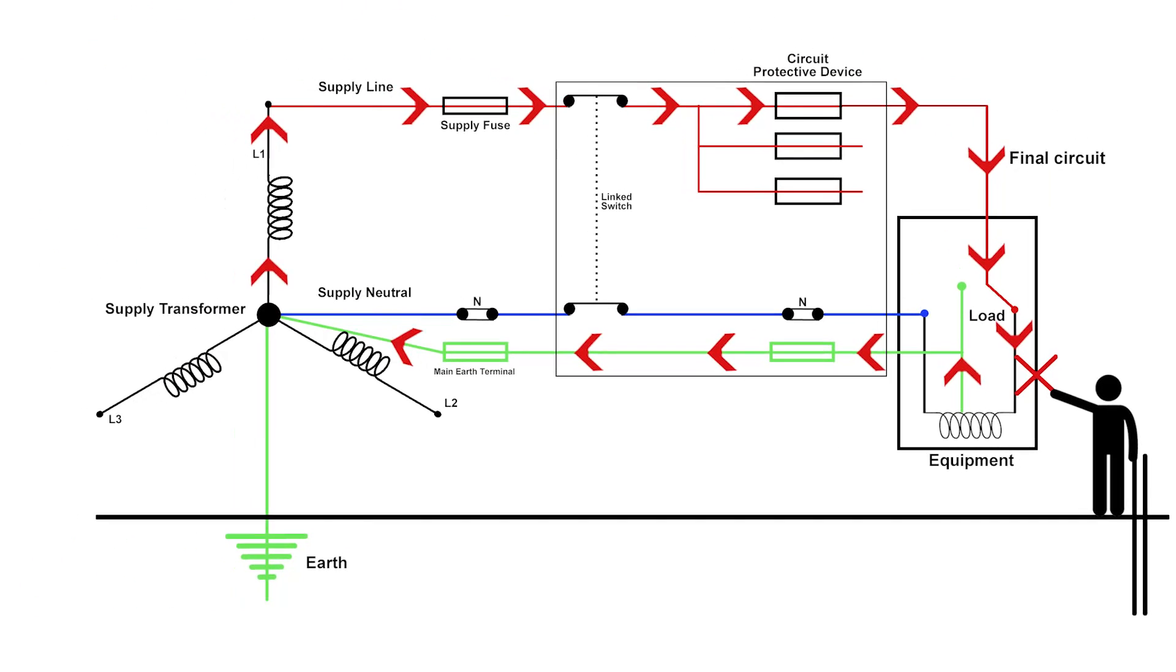Now a 20 amp type B protective device—and in fact any type B protective device—requires a maximum of five times its current rating to operate it, and it must operate within 0.1 of a second. That's the way the product standard says they have to be made. So if I've got a 20 amp device, 5 times 20 means that a hundred amps will have to flow through this system before that device will operate.